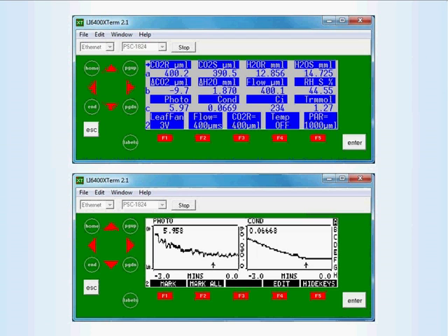Greenhouse-grown plants where wind speeds are low and stressed Mediterranean species often show similar sensitivity to small changes within their boundary layer due to changes in the wind speed and ambient humidity. If you clamp onto a leaf with your LI-6400 and notice stomatal closure, such as shown in this screenshot, then that's a sure indicator that you need to increase humidity and or decrease the leaf chamber mixing fan speed. With care, even the most sensitive plant species can be dealt with using the 6400.